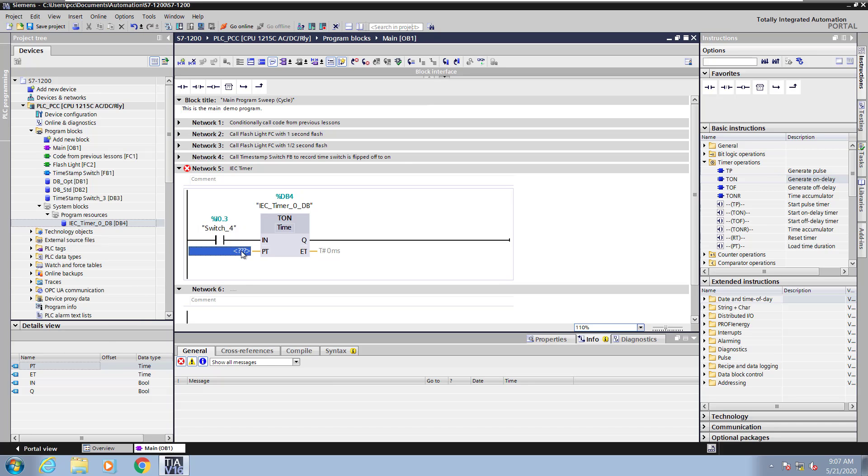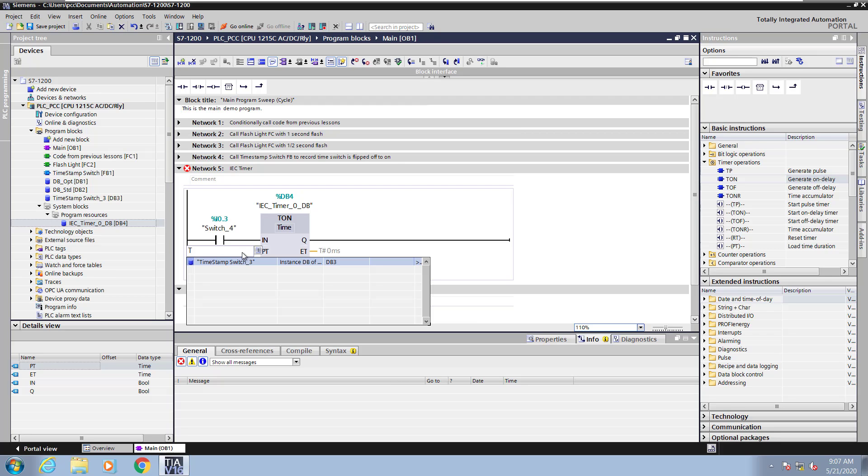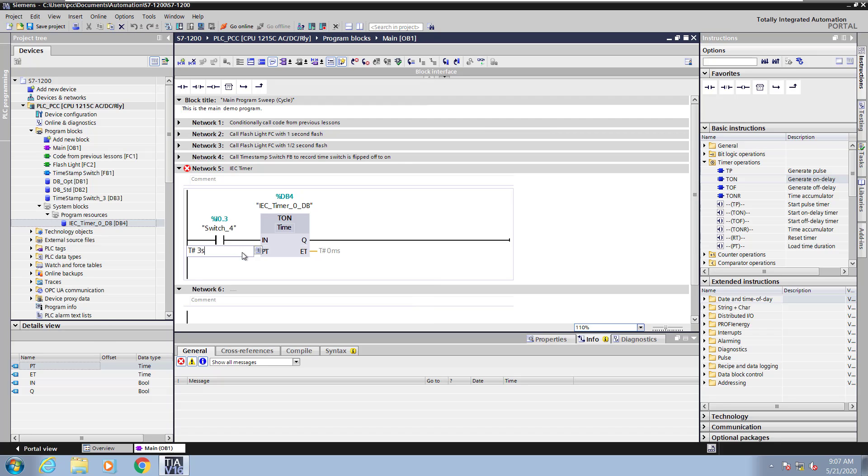Next I will enter in the PT or the preset time for the timer. This is going to be in the time format so I will enter in a preset value of t pound and then 3s for three seconds. So this will give me a three second on delay timer.